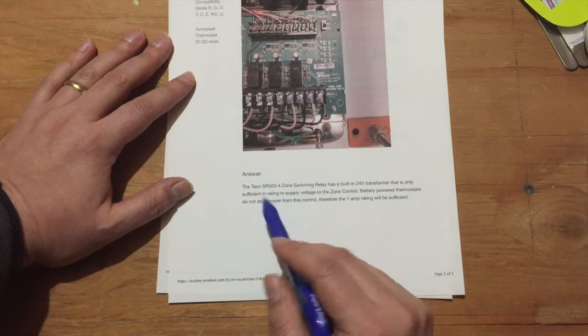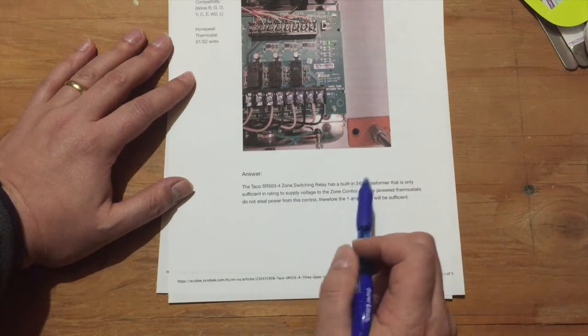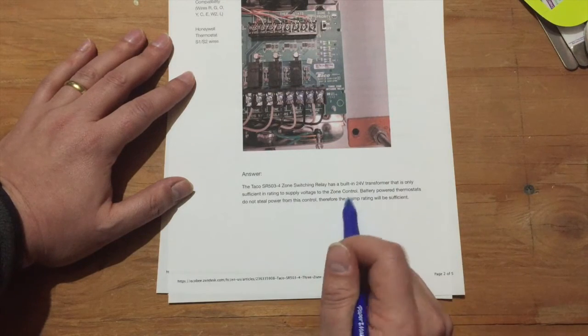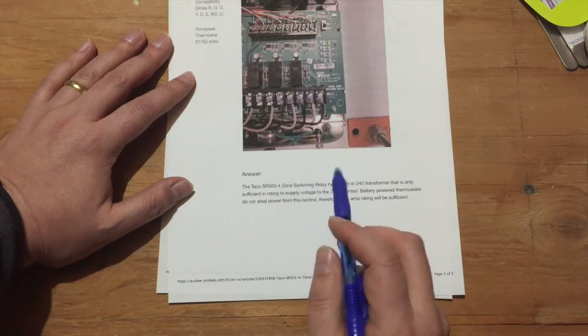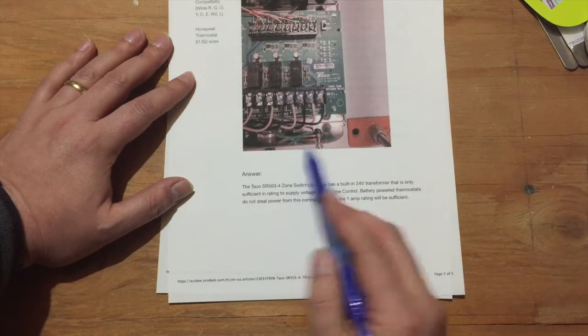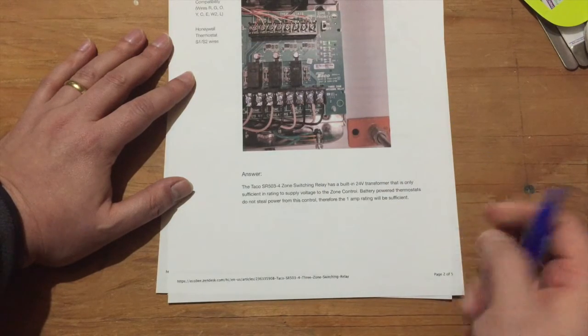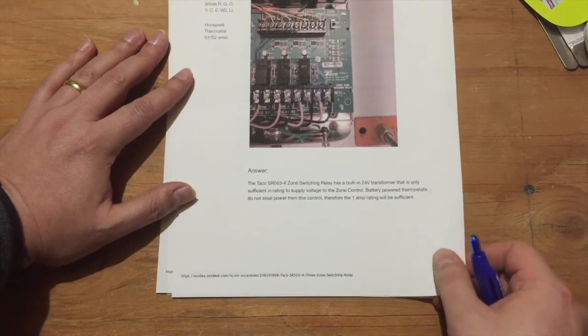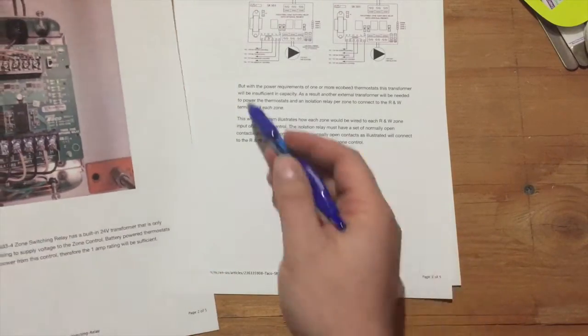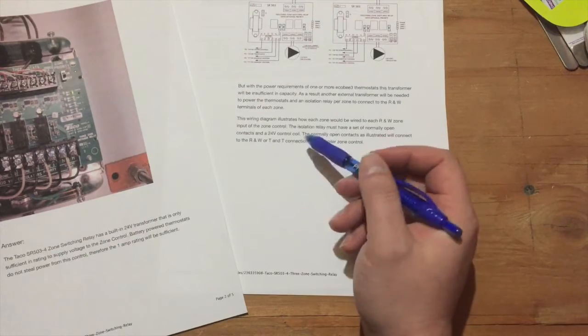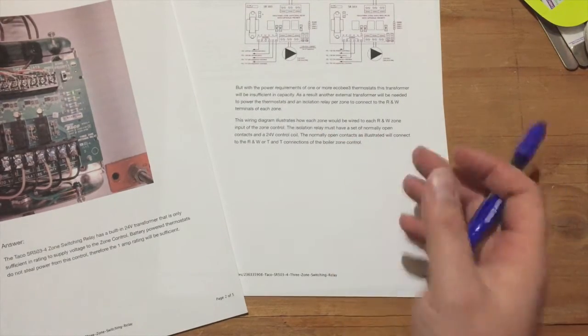And the answer from Ecobee is that the Taco SR503 has a built-in 24-volt transformer that is only sufficient in rating to supply voltage to the zone control. Battery-powered thermostats do not steal power from this control, therefore the 1-amp rating is sufficient. But with the power requirements of one or more Ecobee thermostats, this transformer will be insufficient in capacity. Yada, yada, yada.